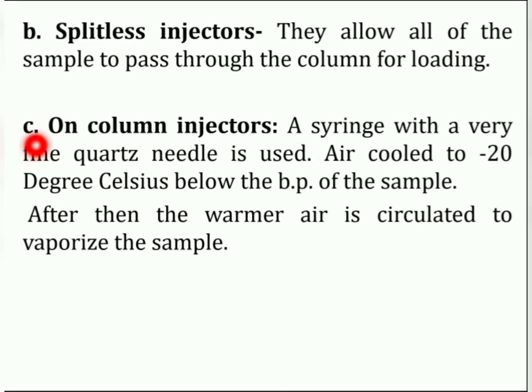On-column injectors. These injectors are perfect for liquids and gases with high and low boiling analytes. In this technique, an injector syringe with a very fine quartz needle is used. These injectors are air cooled to 20 degrees Celsius below the boiling point of the sample. After that, warmer air is circulated to vaporize the sample.